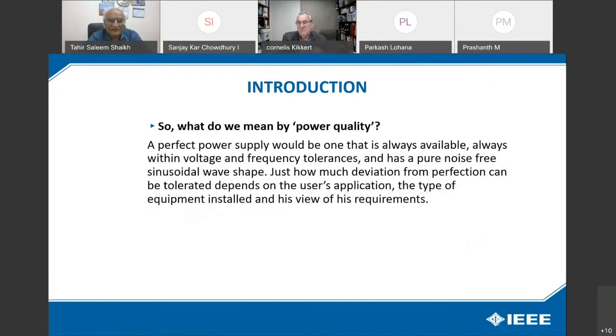So what do we mean by power quality? A perfect power quality supply should be one that is always available, always within voltage and frequency tolerance, that is plus minus 2% for frequency as per IEC code, and plus minus 10% for voltage, and has a pure noise-free sinusoidal wave shape. Just how much deviation from perfection can be tolerated depends on the user's application, the type of equipment installed, and his view of his requirements.